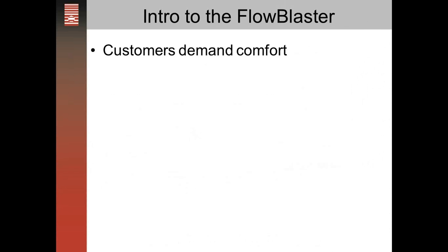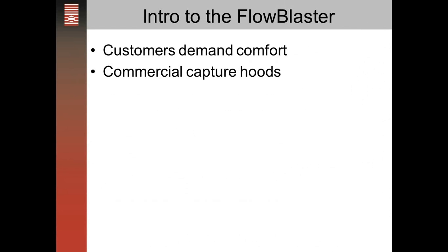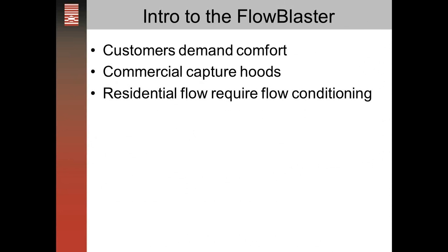As we've come to know over the years, customers demand comfort. Comfort in large part depends on the amount of air being delivered from a register and the temperature of that air. Commercial test and balance engineers have used capture hoods for years to measure airflow through large registers. A large hood directs airflow over a flow grid, and there's an instrument that converts pressure to flow. Lower airflow that we see in residential applications often exits the register in very small jets that can partially miss the flow sensors of the standard capture hood.